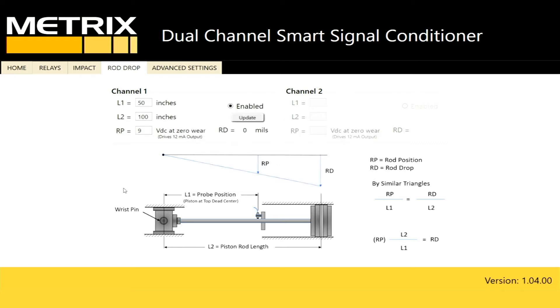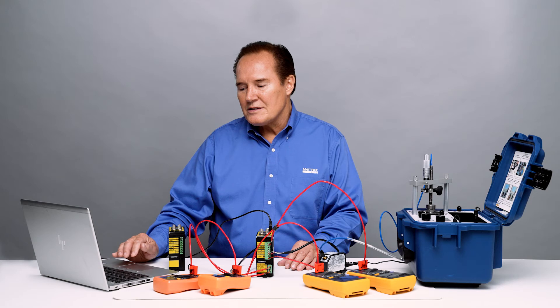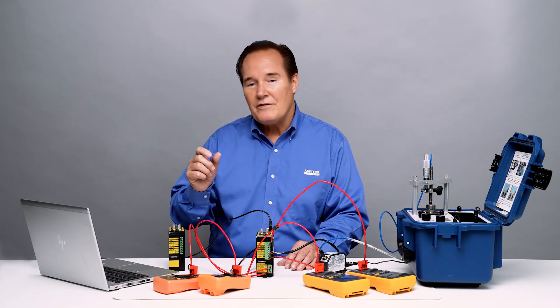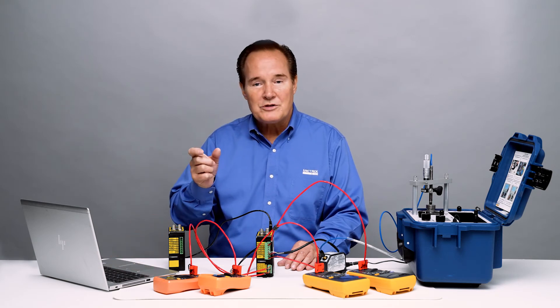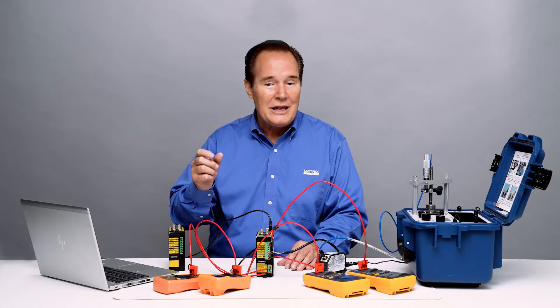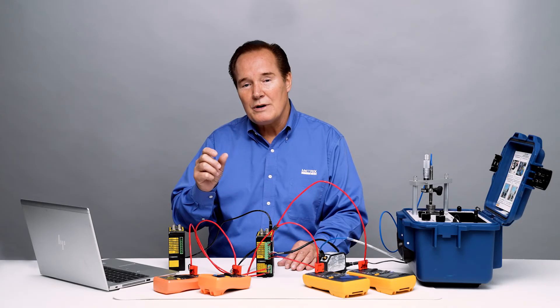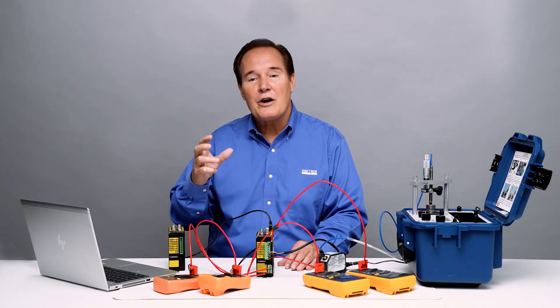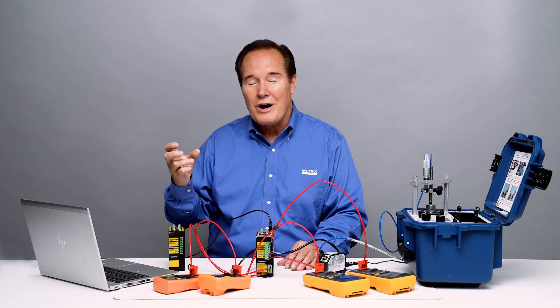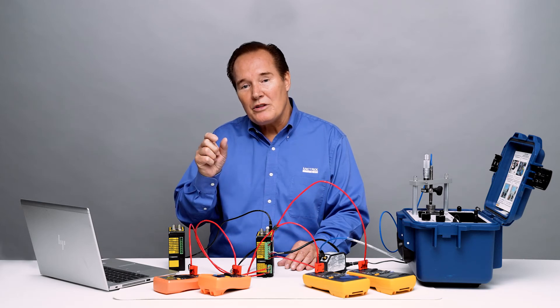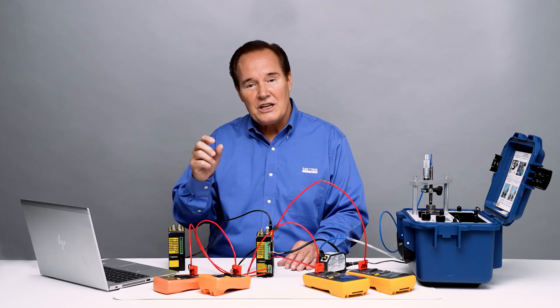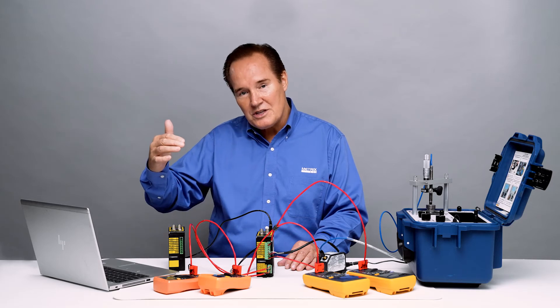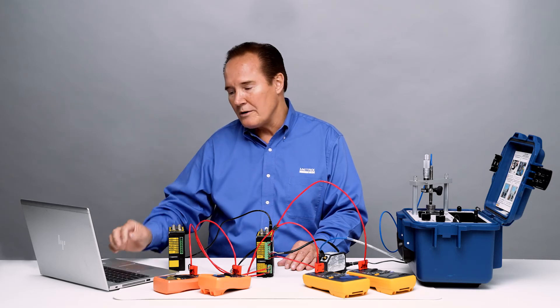Since I put 9 volts in we have zero offset. If I had 10 mils of wear I would put in 8 or 10 volts, but I'm putting in 9. If I already knew what the wear was I could put in the right voltage to get the amount of wear I have now, and then we could see the future wear.